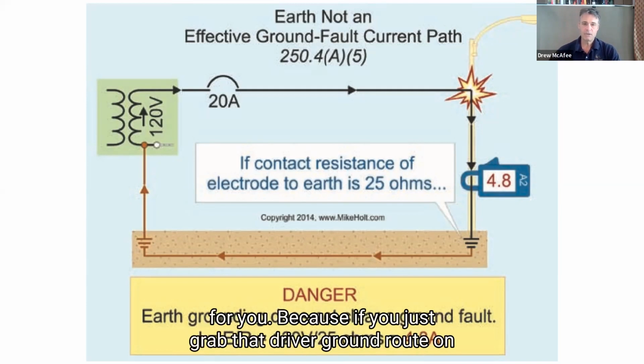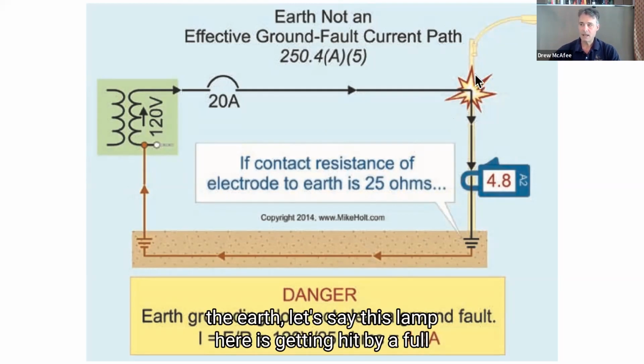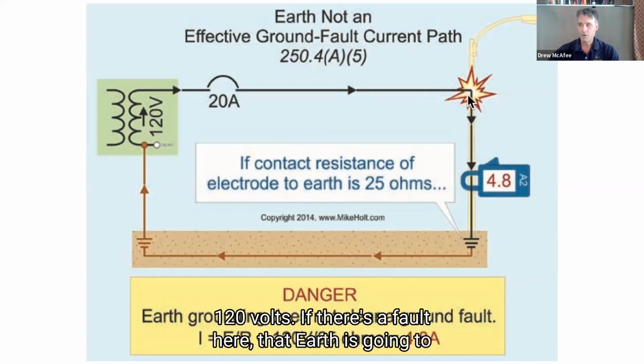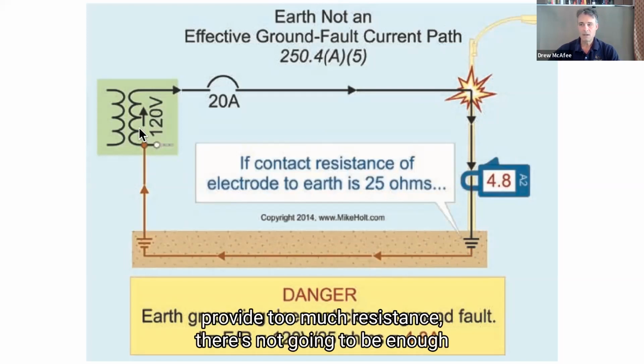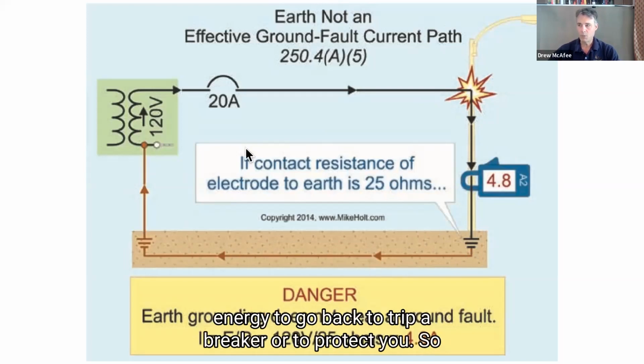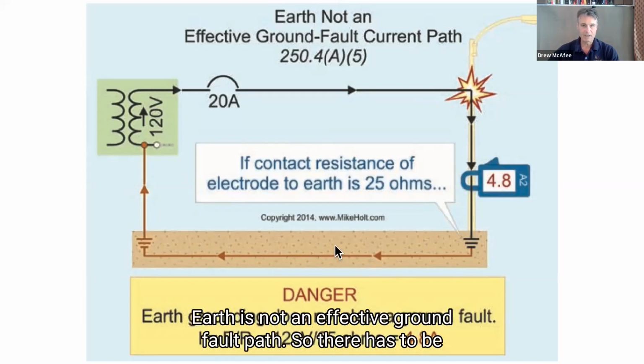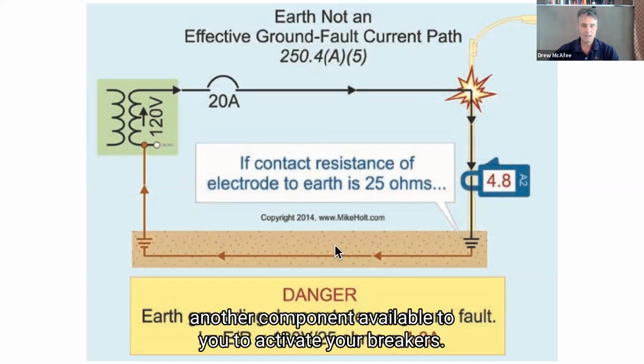Because if you just drive a ground rod out in the earth, let's say this lamp here is getting hit by a full 120 volts. If there's a fault here, that earth is going to provide too much resistance. There's not going to be enough energy to go back to trip a breaker or to protect you. So earth is not an effective ground fault path. There has to be another component available to you to activate your breakers.